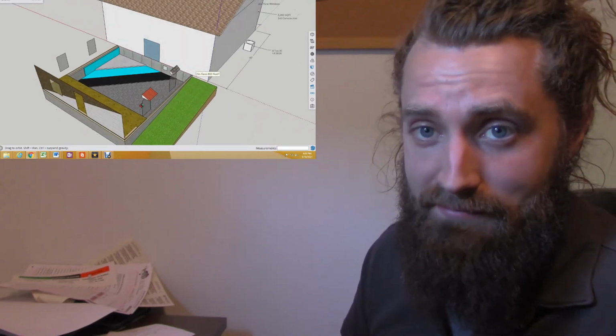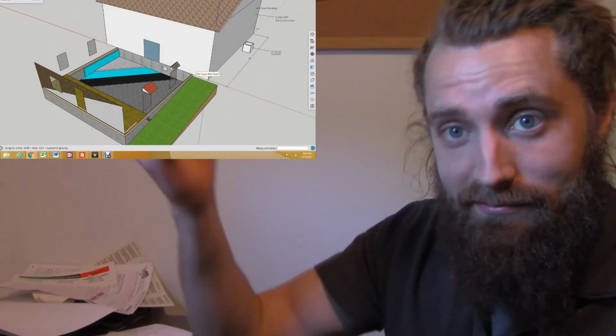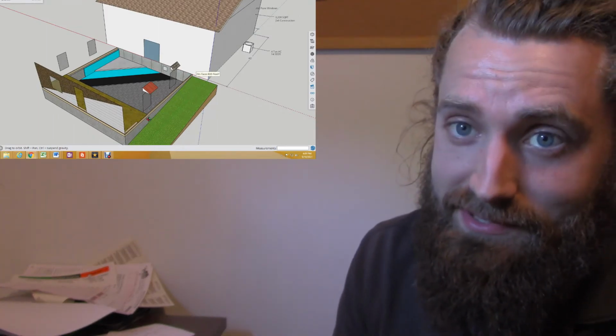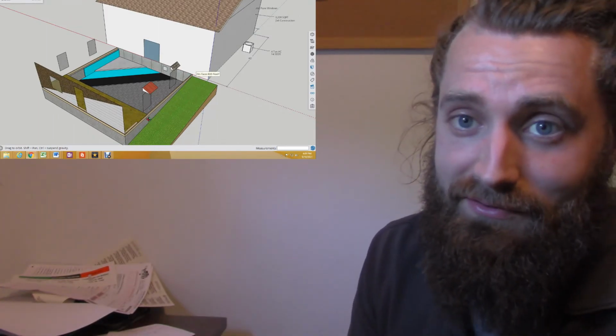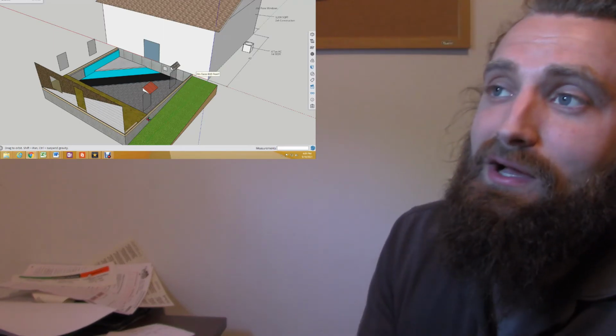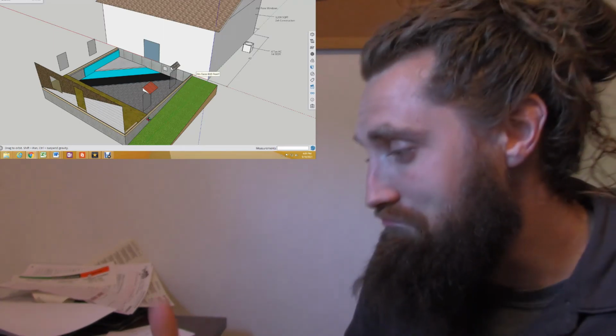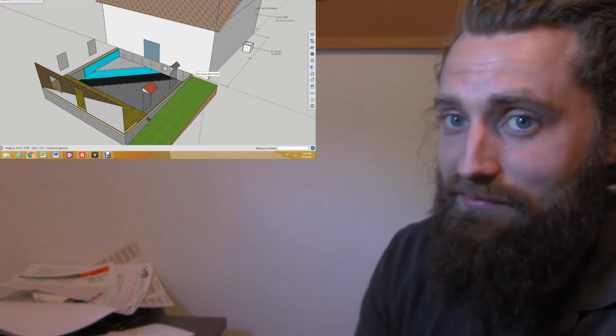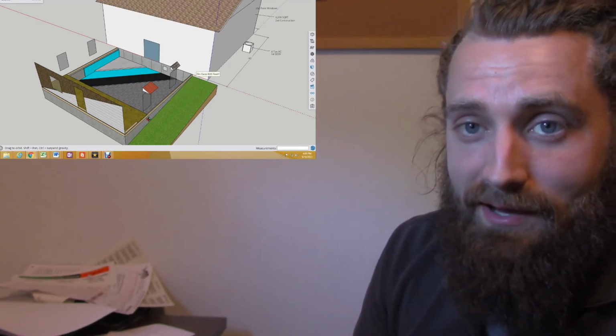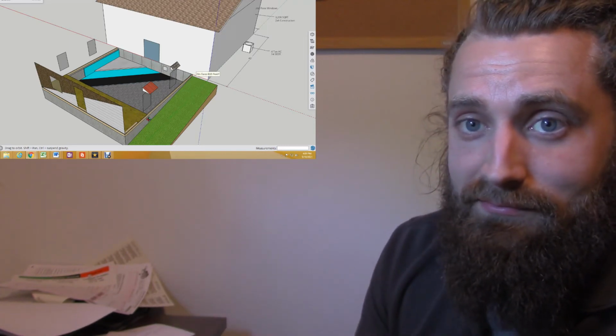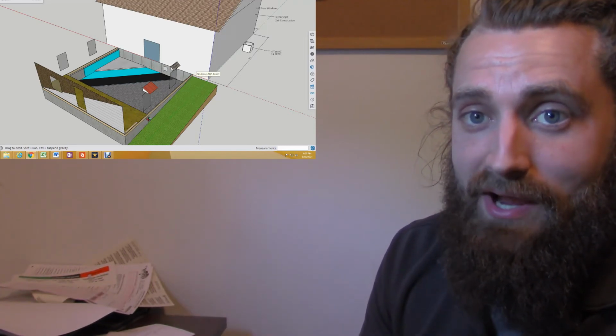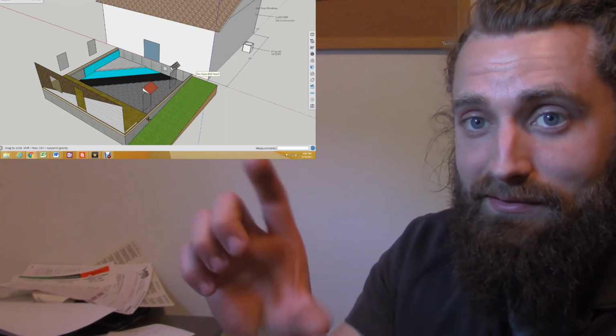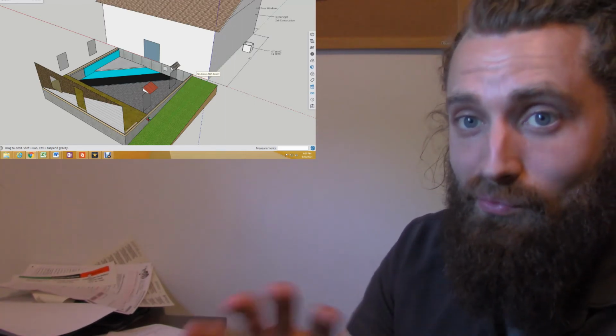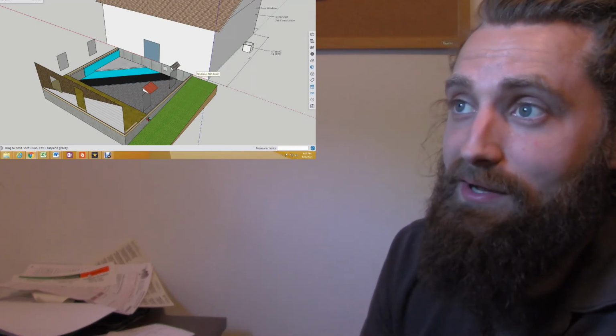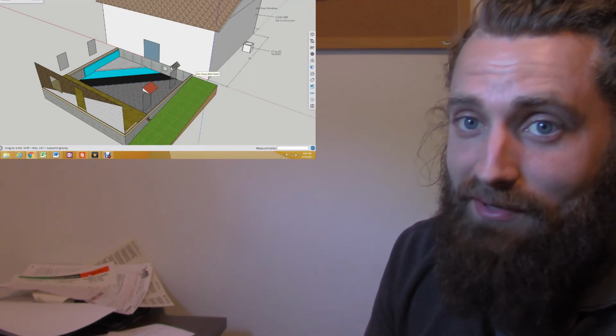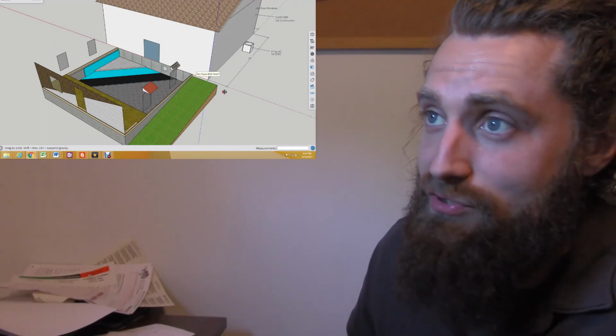If you've got an ECM motor... now, we do know it's extremely unlikely that this one is an ECM blower because our guy told me it was 19 years old. So with a PSC motor, you're going to have an amperage spike of some gradient. With an ECM, when you do that to it, you're going to see a drastic amperage draw, because the ECM motor is going to say, hey, we want to really start pushing some air here, and it'll ramp itself up tremendously.